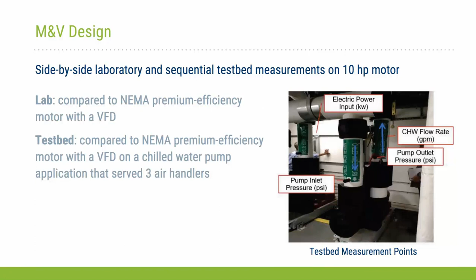Okay, for the laboratory evaluation, the performance of a 10 horsepower smart motor and a 10 horsepower premium efficiency AC induction motor with a VFD were compared using a dynamometer operated under tightly controlled conditions. And then for the site demonstration, the performance of a 10 horsepower smart motor was compared to that of an existing 10 horsepower premium efficiency AC induction motor with a VFD in a chilled water pumping application at the land port of entry in San Ysidro.